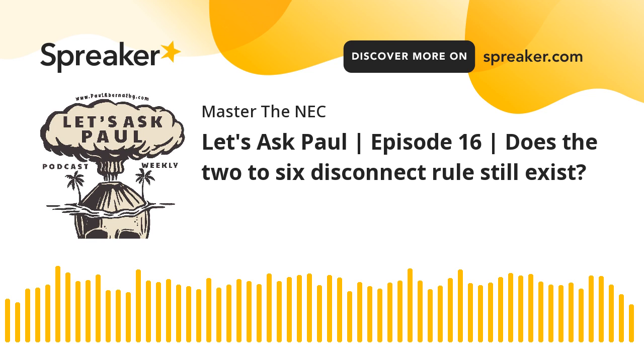Maximum number of disconnects. Each service shall have only one disconnecting means, unless the requirements of 230.71(B) are met. So this is telling me you only have one service disconnect to a building. However, if you're going to meet the requirements of 230.71(B), which is the 2 to 6 service disconnecting means, which still has the allowance of the 6 disconnect rule, it says you have to follow all of those rules. So we're assuming, based on the question that was submitted, we have an application where it's 2 to 6. So we're going to go straight to 230.71(B).